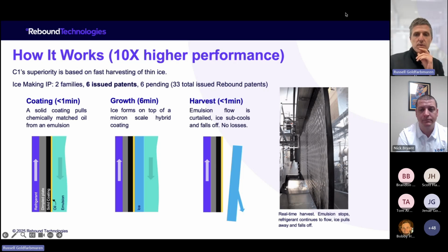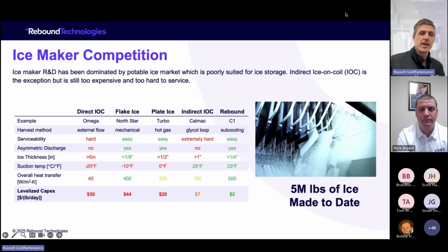And you can see this video on the right of our test rig harvesting, very quickly. What that results in is just a lower capex. So we're 10 times cheaper than a thermally harvested plate ice maker, and we're less than half the cost of an ice on coil system. And the other big thing that it does is the service of our system is just like a falling film chiller. You can open it up, you can access all of the piping, all of the heat transfer surface area really easily.